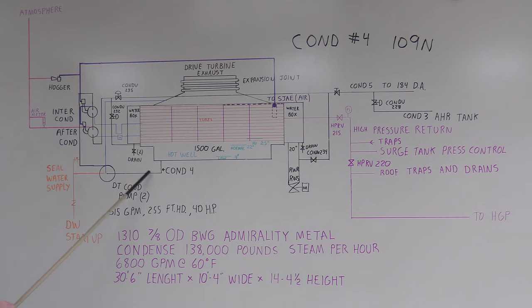The problem with these pumps - this is a vacuum in here, so it's actually trying to pull up from 33 feet, so it's the same as having the suction 33 feet down here trying to pull up. The way they make this style pump work, there's a vent line that goes from the pump suction back to the top of the surface condenser so it sees the vacuum.